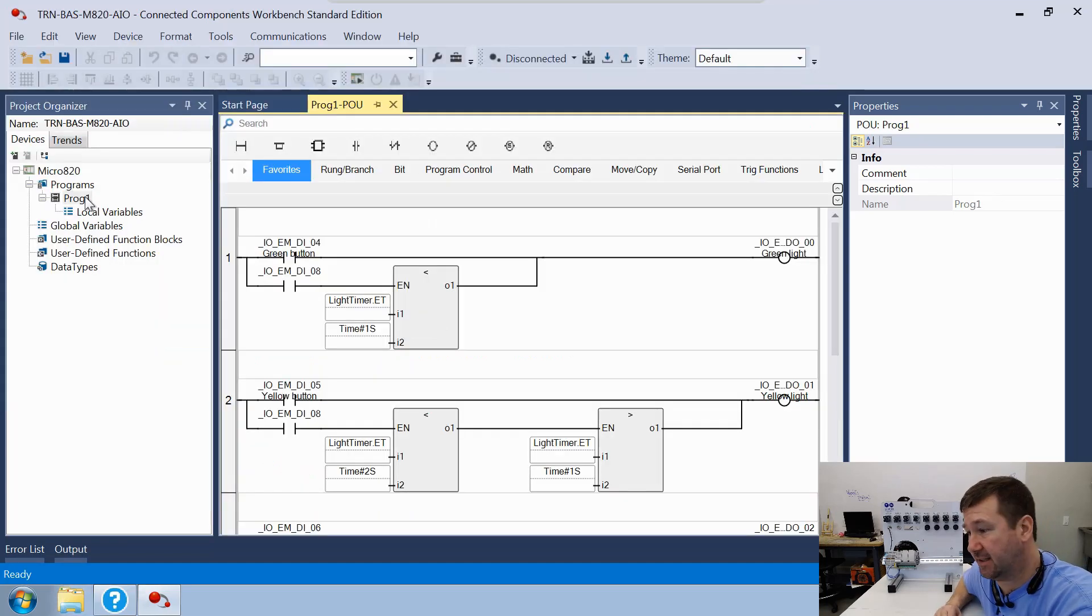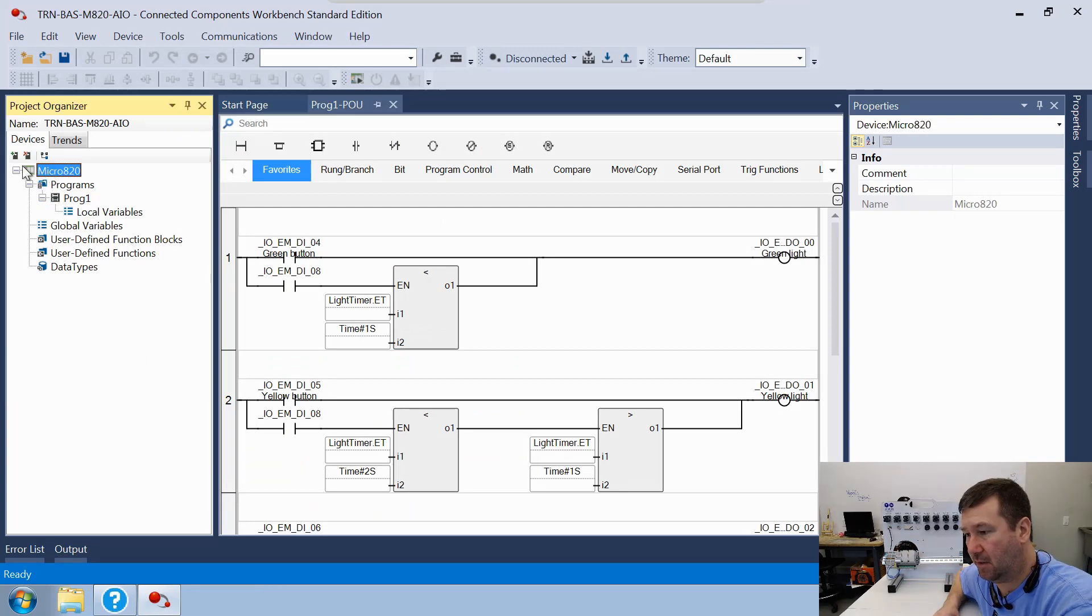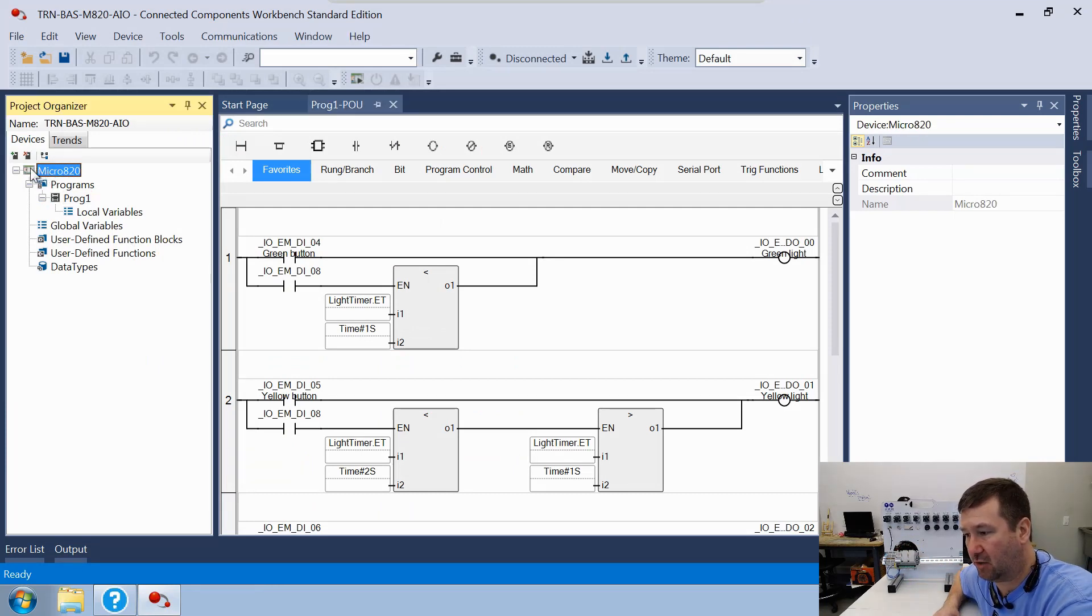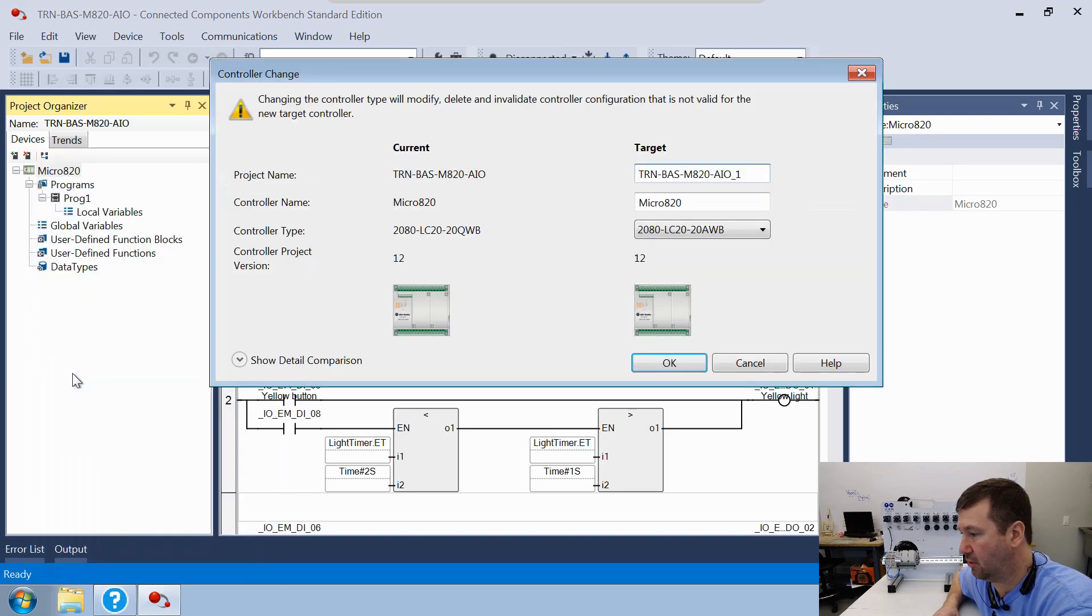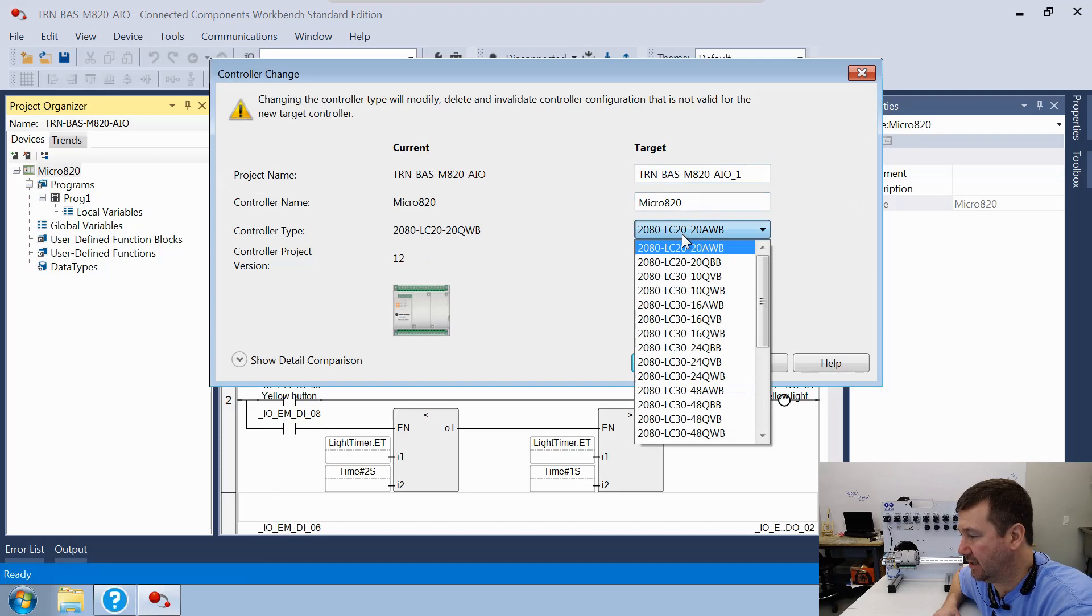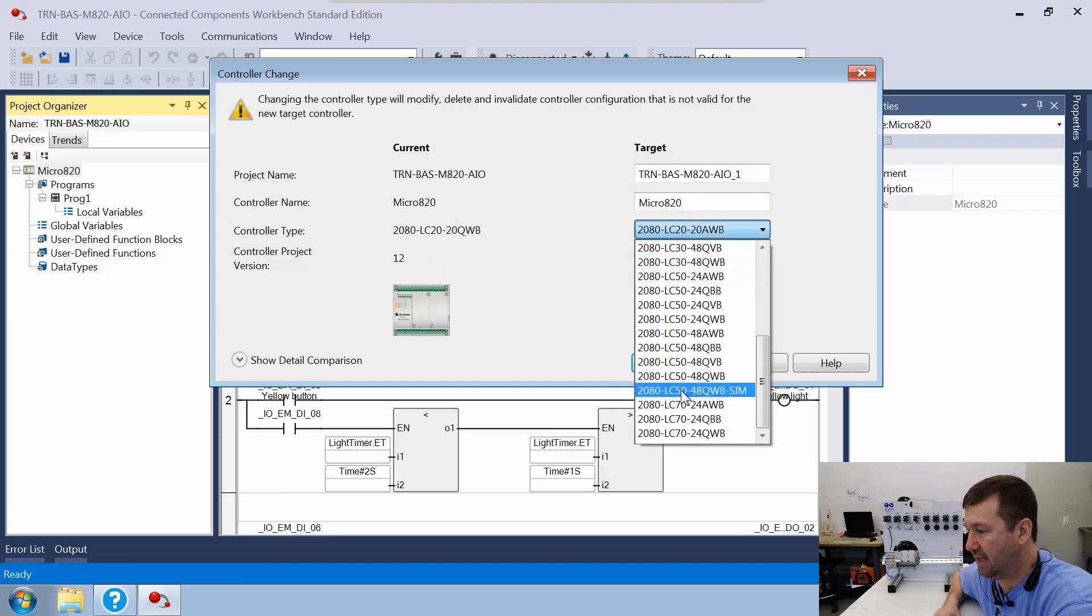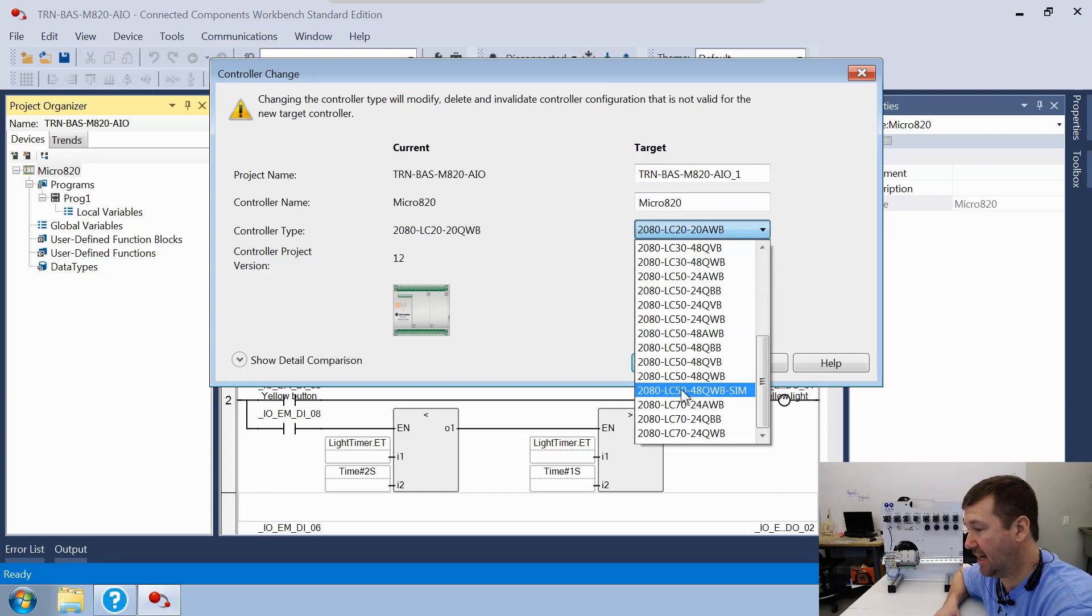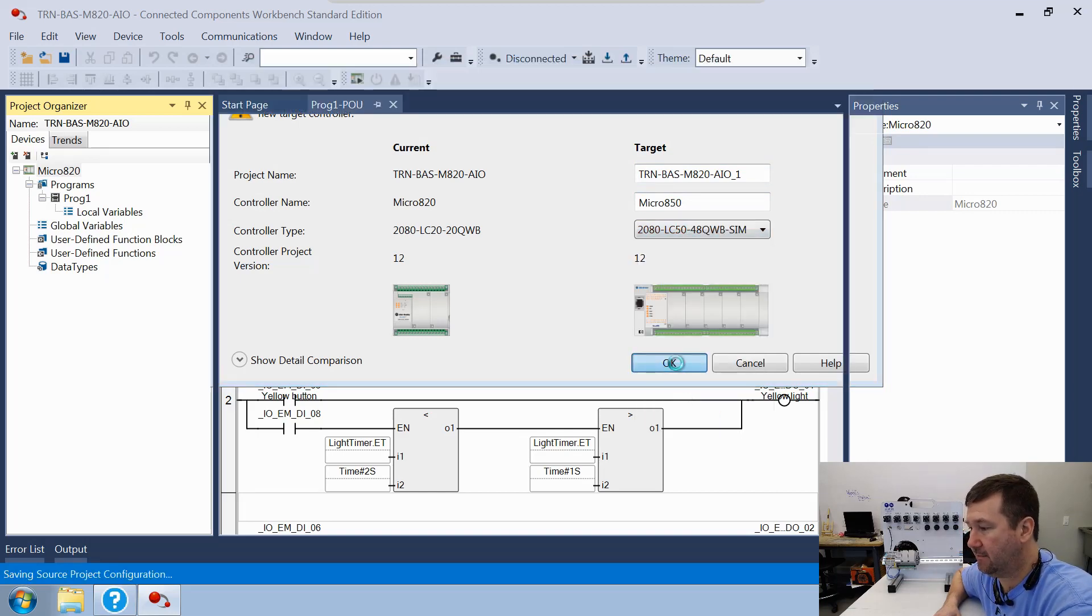This is the Getting Started program that comes with all of our 820 PLCs. We're going to go up here to where it says Micro 820 Controller, we're going to right-click it, and we're going to go down to Change Controller. I am going to change this to that 2080-LC50-48QWB-SIM. We'll click OK.